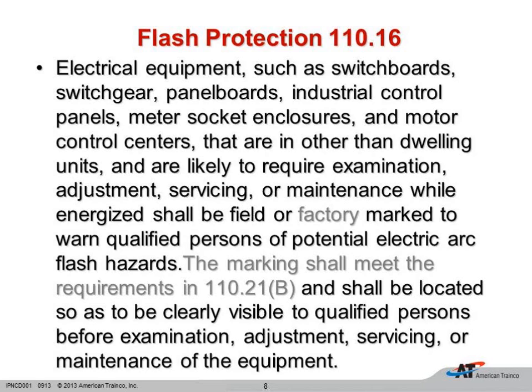That brings us up to 110.16, and this is the requirement in the National Electrical Code for the arc flash warning label. And we can see, I highlighted in gray a little bit, that now that label can be field or factory marked. So our manufacturers can put a generic label on that equipment. Most of them have already been doing it. And this requirement still only requires the generic label. And in the next slide, I'll give you an idea exactly what that's going to be. But it does say that the marking has to meet the requirements in 110.21(B). So that's going to be very similar to the ANSI Z535 standard. And a specific word is going to be associated with a color, and they are going to tell us exactly what might happen to us in that case.